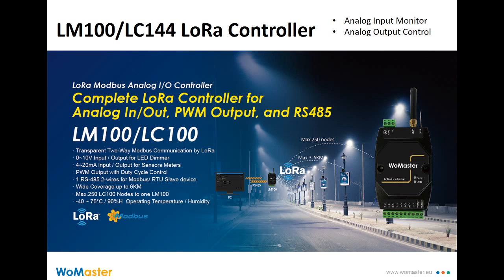It supports two-way Modbus communication over LoRa. Users can access data from the LED dimmer, sensor, and meter over LoRa. The distance is up to 6 km and 250 nodes in one network scope.